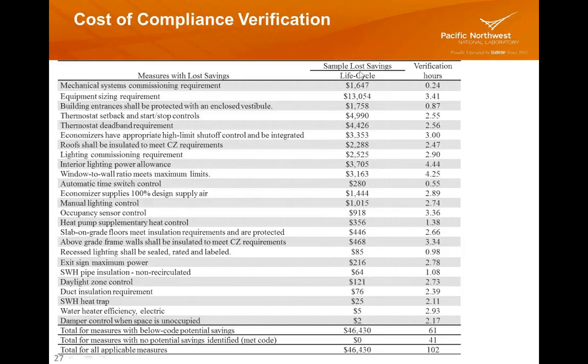Here I've added the lost life cycle cost savings for each of the measures, along with the verification hours. So you can see pretty high, the commissioning was a big lost energy cost savings. Equipment oversizing was pretty significant. Some of the others, like damper control when spaces are unoccupied, were pretty low.